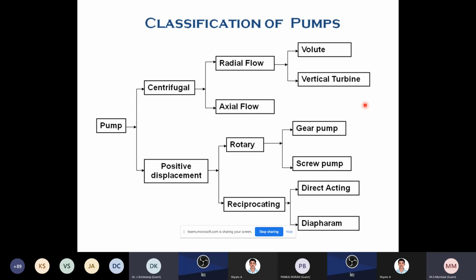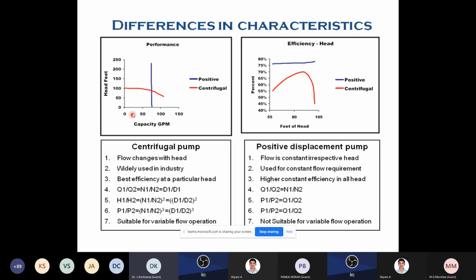But before going to this statement, just see the performance of the centrifugal pump. The pump performance decreases, the capacity decreases. The flow decreases with the reducing of the head. So if the head is reduced, automatically the flow changes; flow depends on the head. Whereas a positive displacement pump does not depend on the head. So if you want a constant flow pump, you have to select positive displacement, like the turbine bearing oil supply pump and the seal oil supply pump, where we need constant flow. It does not depend on the head of the tank or head of the pump. So we go for positive displacement pumps for constant flow purposes, and in normal cases we go for centrifugal.